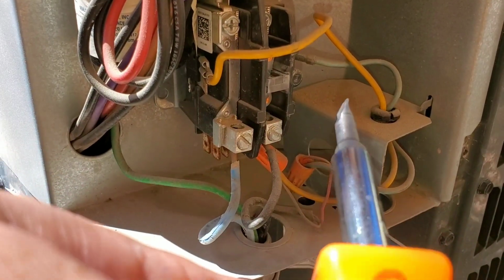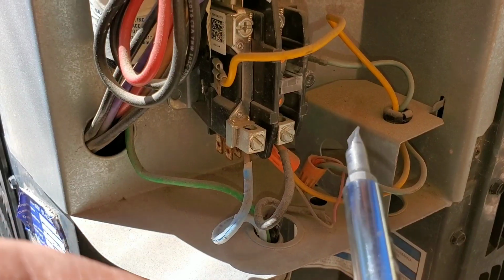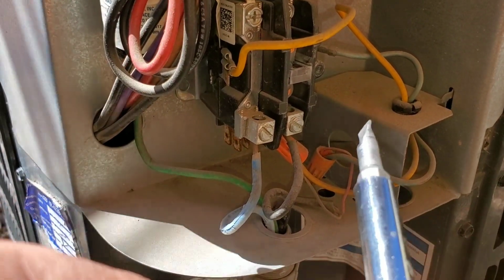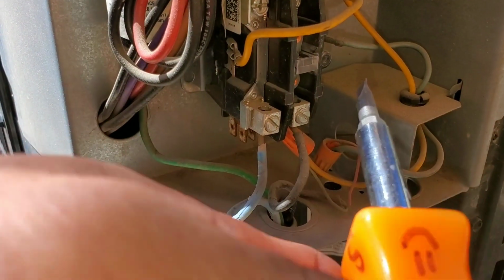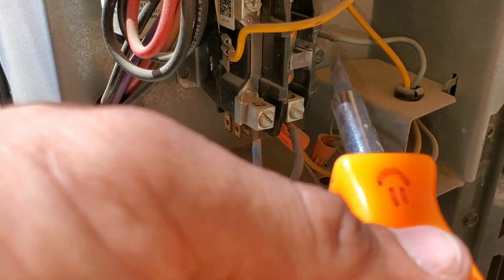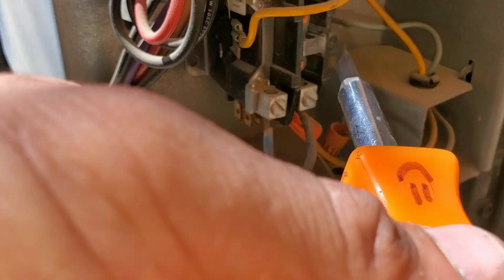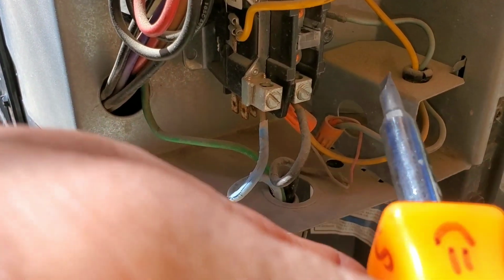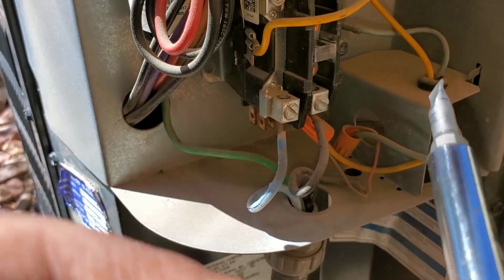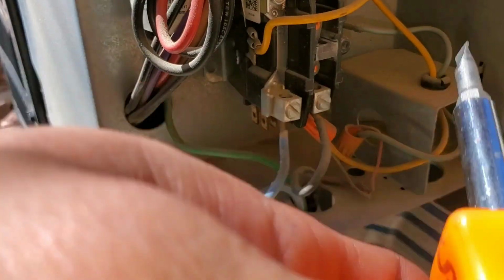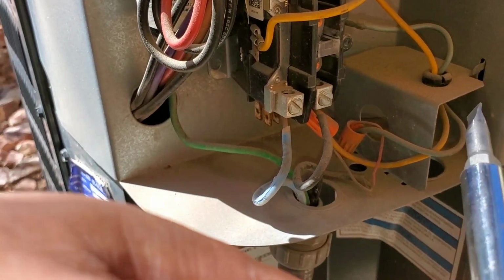Again, be very careful when you're working on this. Safety is always important. I know a lot of guys made comments on my video asking me to make sure that I advise that. What I'm going to do right now is engage my contactor manually, and what I'm doing is bypassing my 24 volts and tricking my system into thinking that I have 24 volts. If I engage my contactor and my condenser does turn on, I know that the problem is not down here. The problem is going to be somewhere between step one and step two. My compressor turned on, my fan motor turned on.